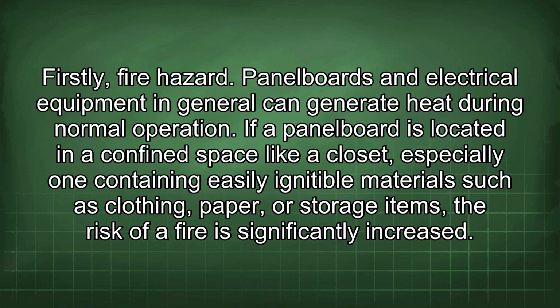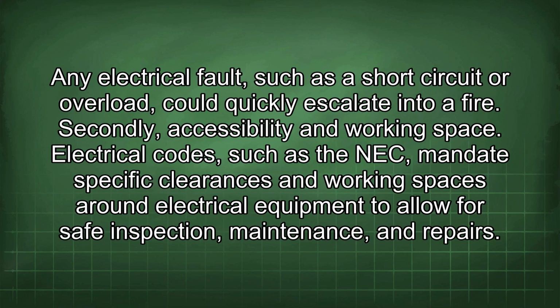Firstly, fire hazard. Panel boards and electrical equipment in general can generate heat during normal operation. If a panel board is located in a confined space like a closet, especially one containing easily ignitable materials such as clothing, paper, or storage items, the risk of a fire is significantly increased. Any electrical fault, such as a short circuit or overload, could quickly escalate into a fire.